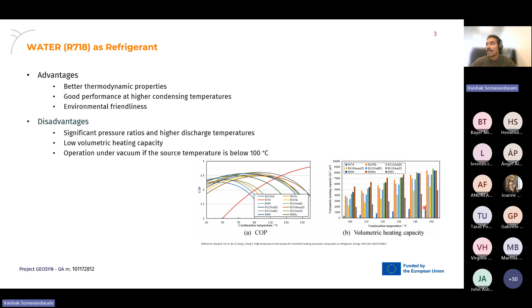As my colleague mentioned, we are developing a heat pump to demonstrate our idea. The heat pump we are targeting to develop has a capacity of 50 kilowatt, and a 4-stage oil-filled reciprocating compressor is being developed by Dorin for this application. One of the main technological constraints during the development of the system is that we need to limit the discharge temperature of the compressor below 270 degrees centigrade.